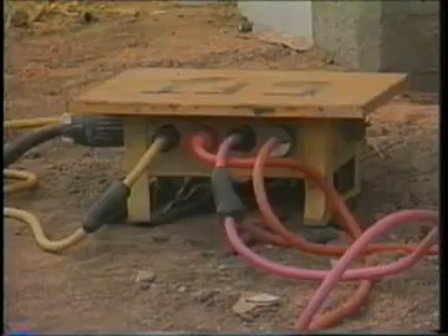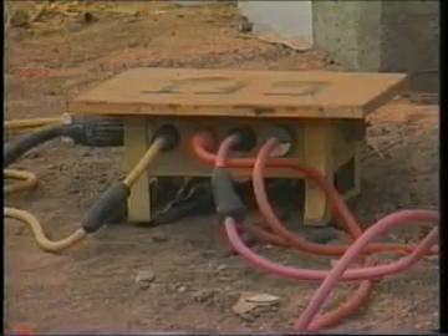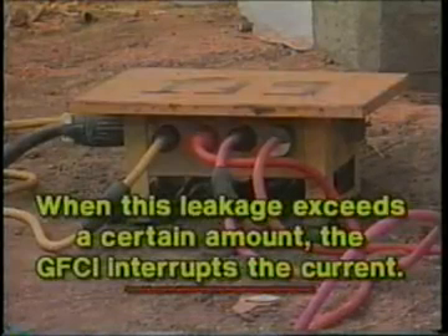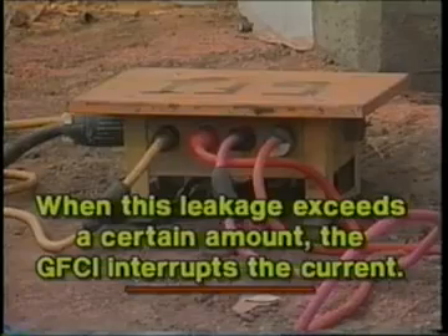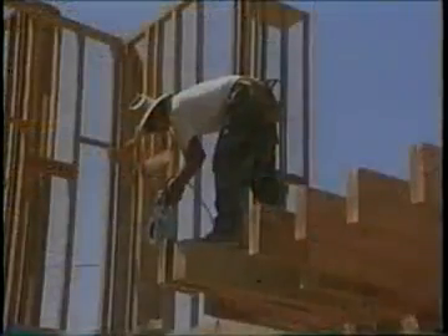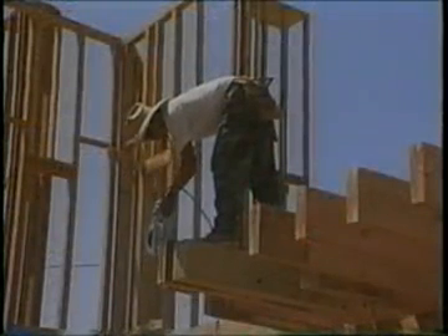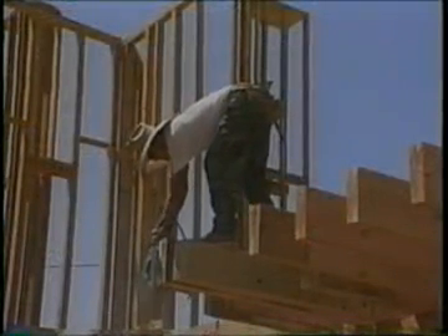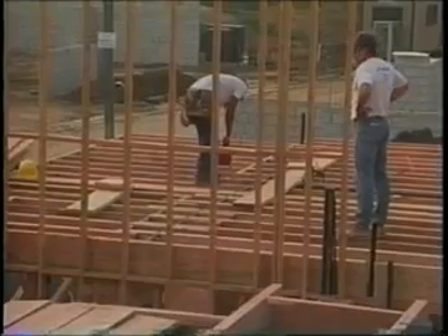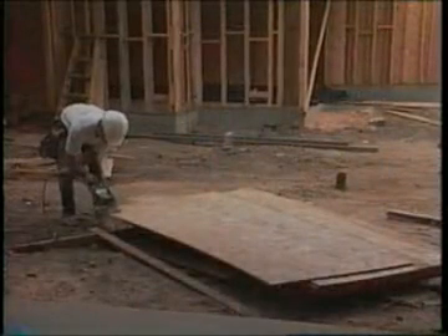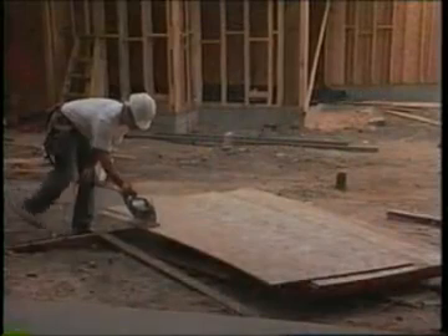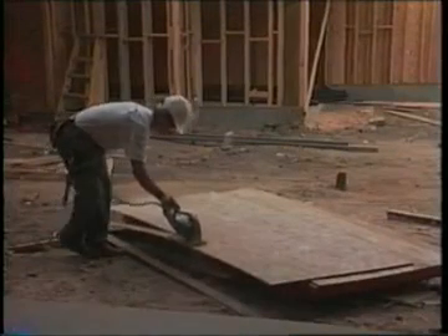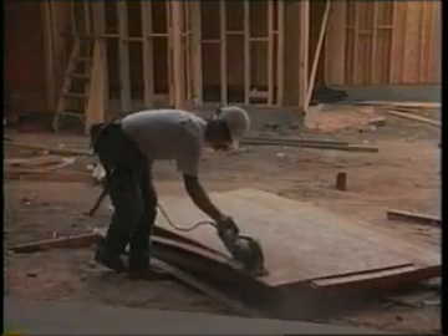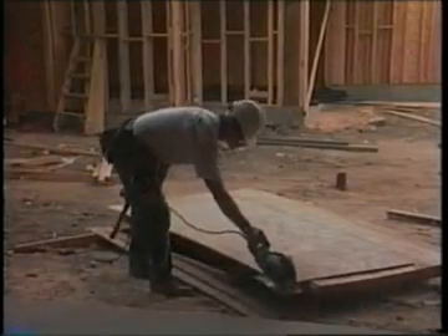These GFCIs monitor the current to the load for leakage to ground. When this leakage exceeds a certain amount, the GFCI interrupts the current. They are rated to trip quickly enough to prevent electrocution. Whether you choose the inspection and testing method or the GFCI method, the objective remains the same: protection from electrocution. Safety on any job site is of paramount importance. Each individual on the job site has a responsibility to inspect all electrical equipment before use, including cords, cables, connectors, receptacles, terminals, plugs, and the equipment itself.